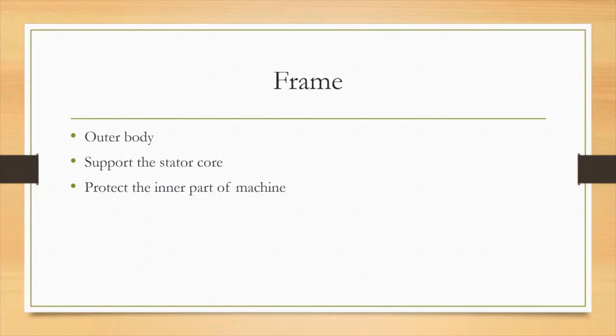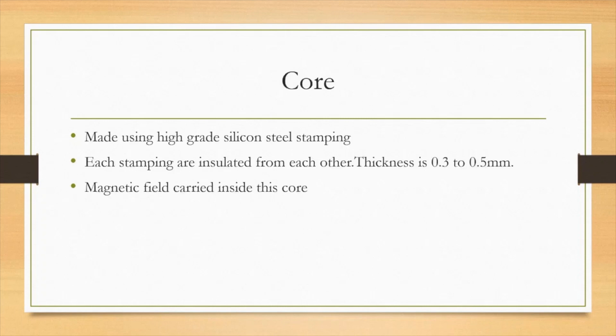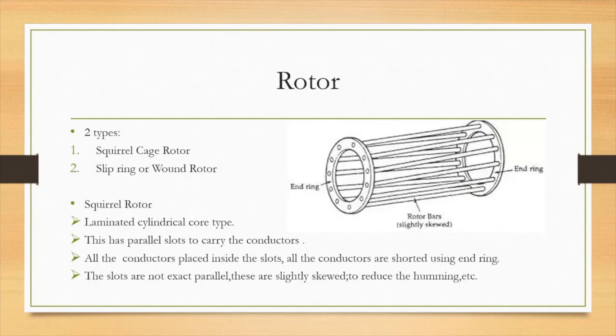A frame is the outer body. It supports the stator core and protects the inner part of the machine. The second part is the core. The core is made of high-grade silicon steel stamping. Each stamping is insulated from each other with a thickness of 0.3 to 0.5 millimeter. Inside this core, the magnetic field is carried.